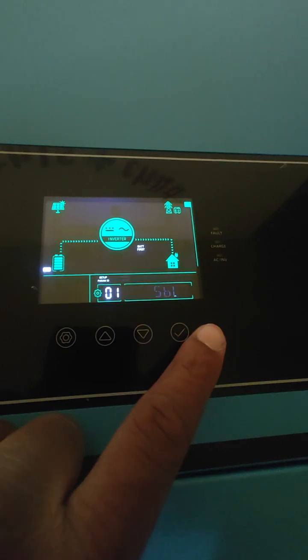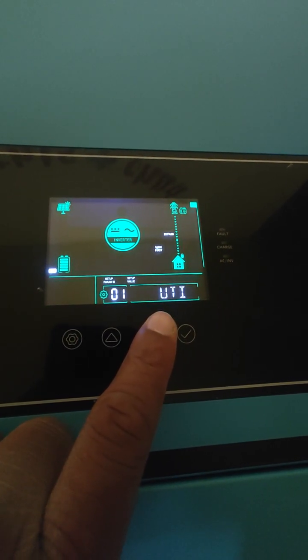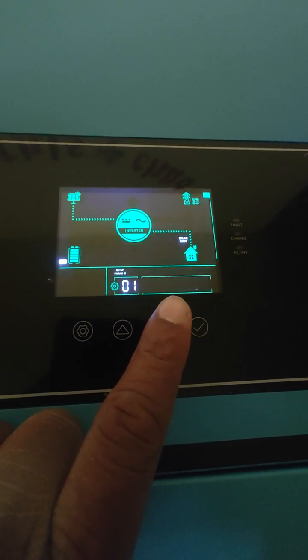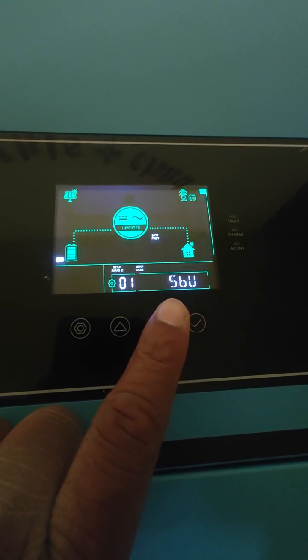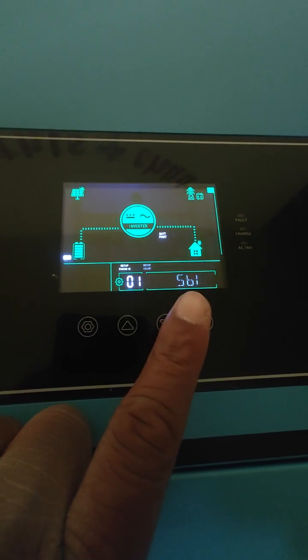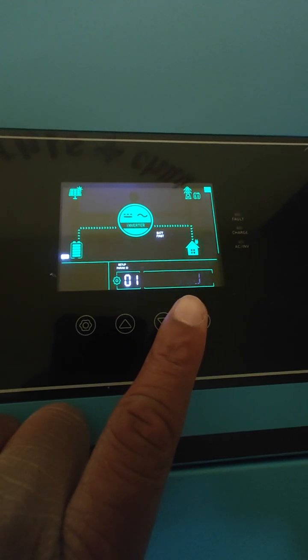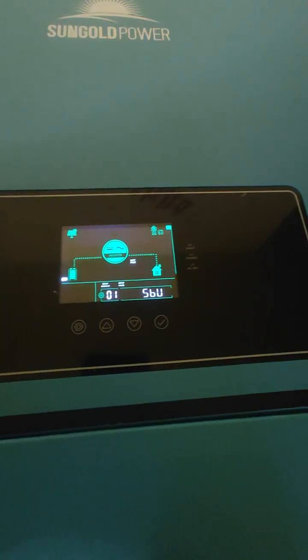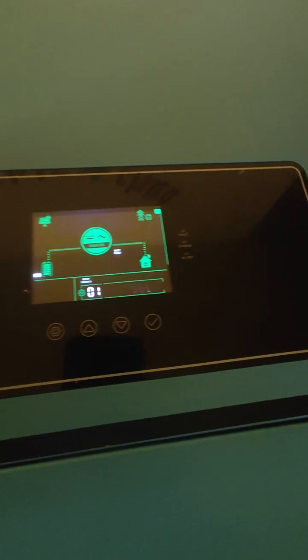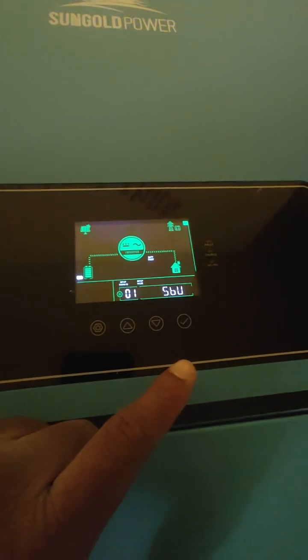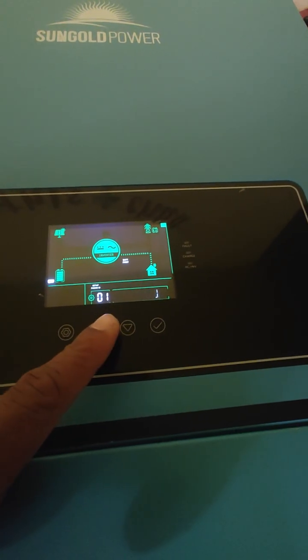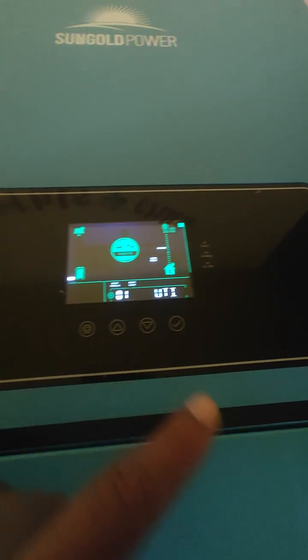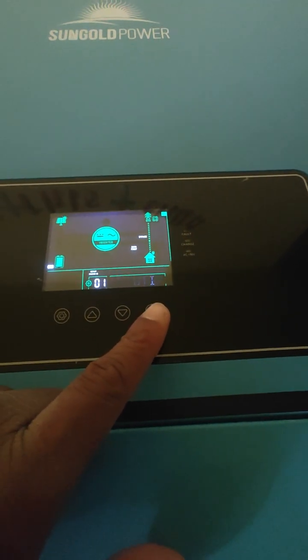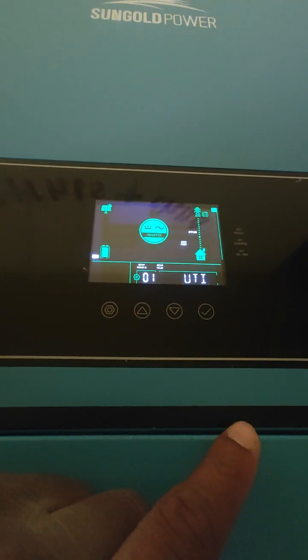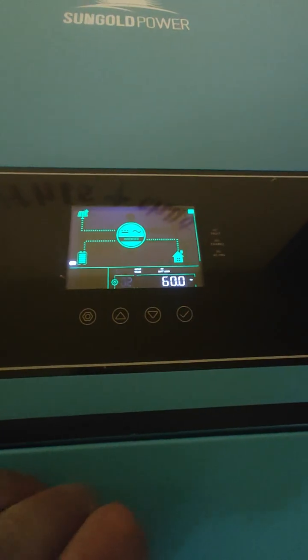Then let's see if we change the settings. We have utility. We have solar for the loads. SBU, I guess, what is that? Solar and battery power at first priority. And then utility will only provide power when the battery voltage is below a certain percent. So we're going to go with utility because where this inverter is going, I'm not going to install any panels. I'm only going to use the battery for backup. So we'll set that.